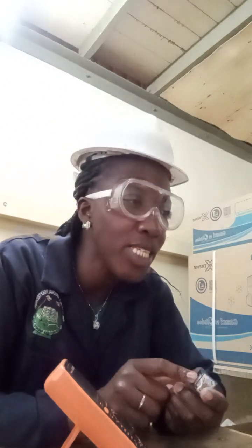Today I'll demonstrate how to test continuity of this particular contact relay. As small as it looks, it is one of the components that serves a very big refrigeration equipment. This contact relay uses a very small current to energize the electromagnet inside, which moves the armature to either open or close in a high power circuit. So before power gets to the compressor, this has to be there and it has to be in good working condition for the equipment to serve its purpose.